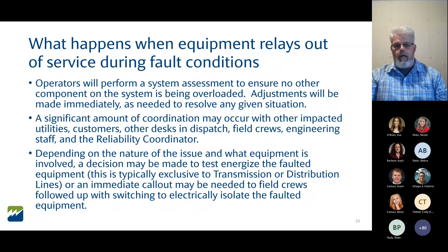So some additional thoughts when equipment relays out of service during fault conditions. Again, we talked about, is there other equipment overloaded? Yeah, that's something to think about. But what have I just done to my neighbor's electrical system? Those overloads may not happen on my system. Maybe the path of least resistance is to go through my neighbor's system. So there are circumstances and situations in the system where we may need to do some system rearranging, some general switching, to alleviate overloads on our own system or overloads on our neighbor's system.